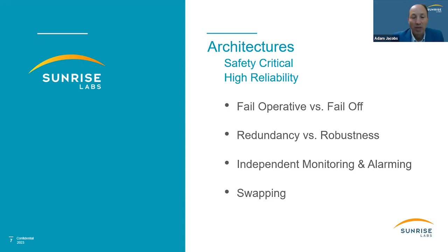But there are some, like a total artificial heart, that's an architecture that would be fail operative, and you do things differently. So you're always balancing a few things. You might have redundancy in your architecture, meaning multiple ways to accomplish your goal—multiple batteries, or in an LVAD, multiple motor drivers, multiple connections, sometimes multiple motors. There's always a trade-off between redundancy and robustness, because redundancy needs to be done carefully so you don't induce cascaded failures from failure modes.